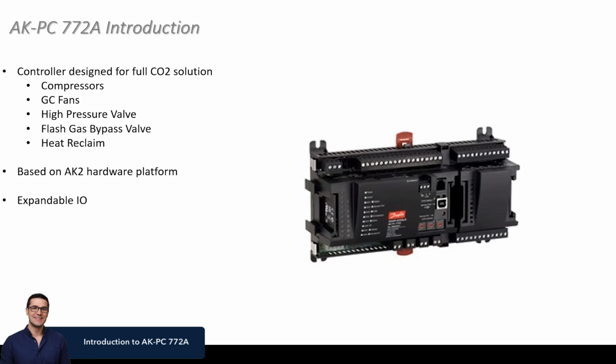This is another depiction of our pack controller, the 772. Yes, it can do the full rack as well. So it's not just a device intended for the high pressure valve and the flash gas bypass. It can handle everything you see bullet pointed here with the compressors, the fans, heat reclaim. So it's really taking full ownership of the rack now on a CO2 system if we need it to.